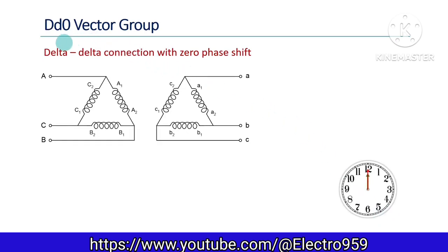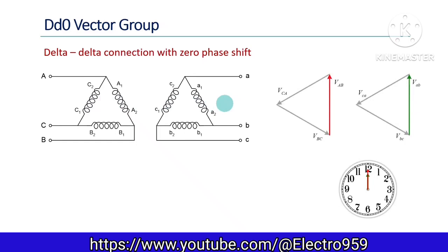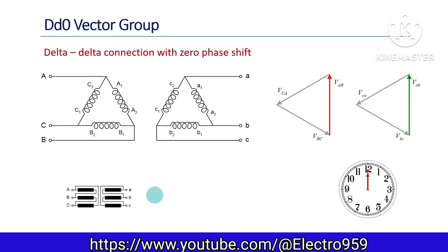The next type is the DD0 vector group. It has a delta-delta connection, meaning both primary and secondary windings are delta connected. In the phasor diagram, line voltages are in phase with the corresponding primary side voltages. The phasor position of line voltage VAB is considered for phase angle representation. Since there is no phase difference between the primary and secondary, the clock position corresponding to zero hours applies here as well. We can have the simplified connection diagram and also the displacement diagram.